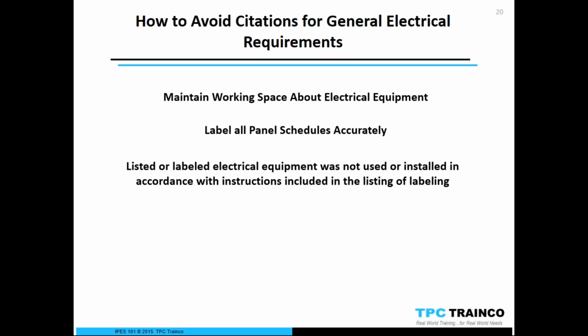This is 110.3b, so this is a key for OSHA. Listed or labeled equipment. So immediately they're talking about, do we have a UL listing on there, or a CSA, or TUV, or ETL. There's a lot of third-party testing entities out there that put their listing on that equipment. So they have tested it under laboratory conditions. And they said, as long as you use this equipment in accordance with the instructions, you're not going to have a problem. Well, the minute that we start modifying that equipment, or we use it outside the parameters that the manufacturer gave us, that can be a big issue with OSHA.